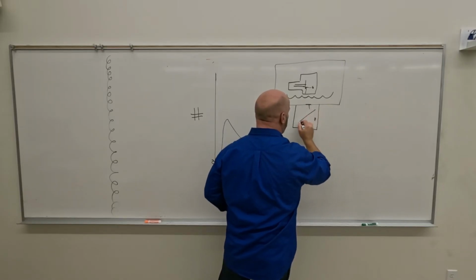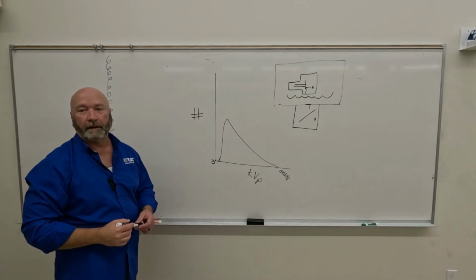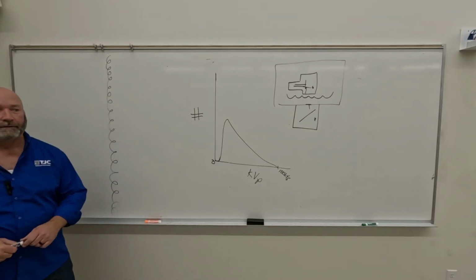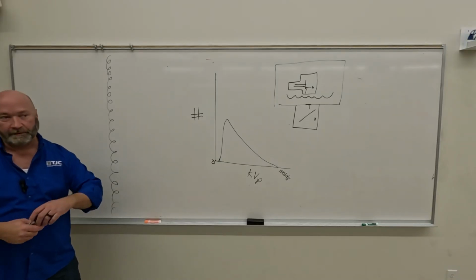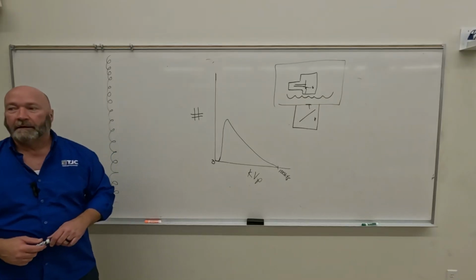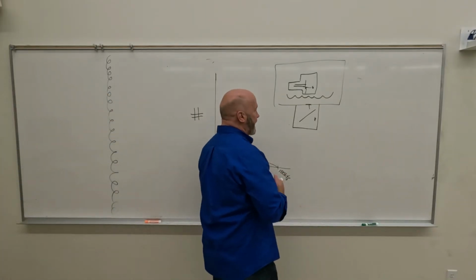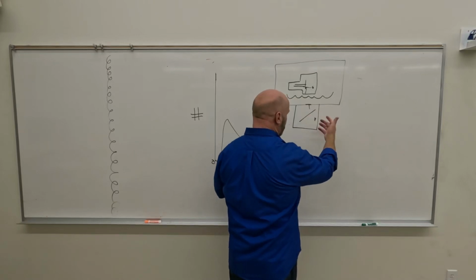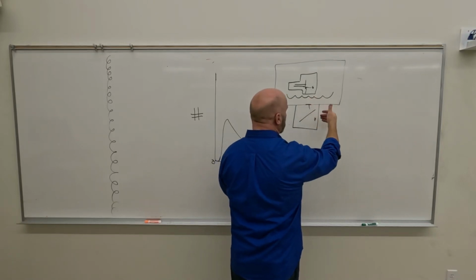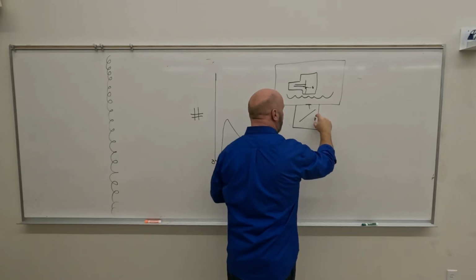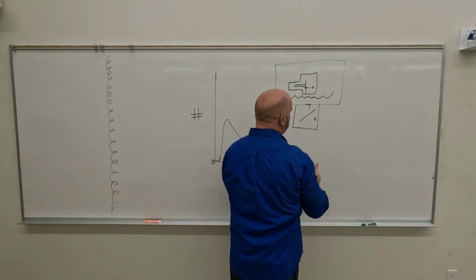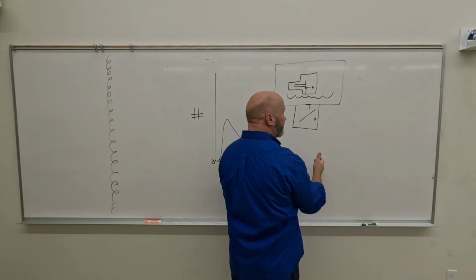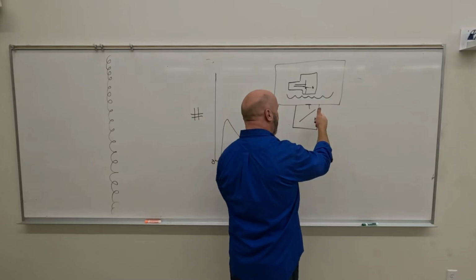Light bulb over here, something to reflect the light bulb. Yeah, mirror. What's on the back side of the mirror? Lead. Probably silver. I guess they probably could use lead, but it's probably silver. But some sort of metallic stuff, and the purpose of the mirror is to reflect light from here, so that we get an accurate radiation field, a radiation field that's accurately reflected by the light field.